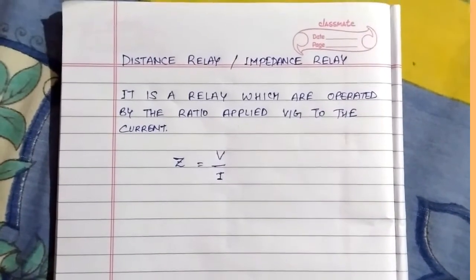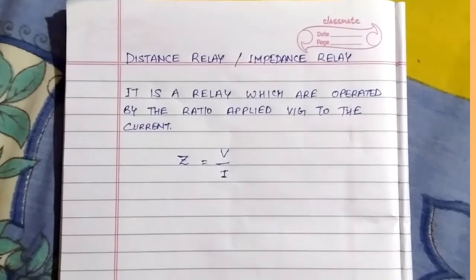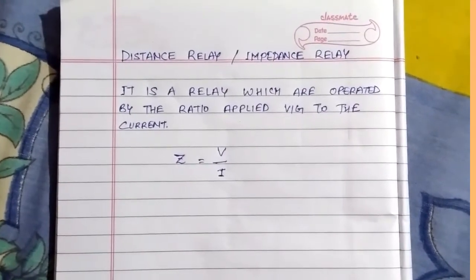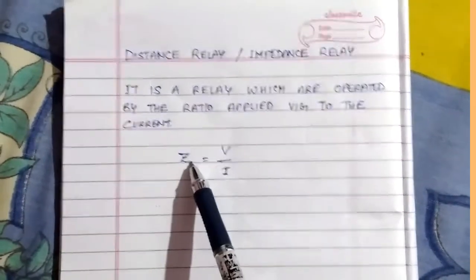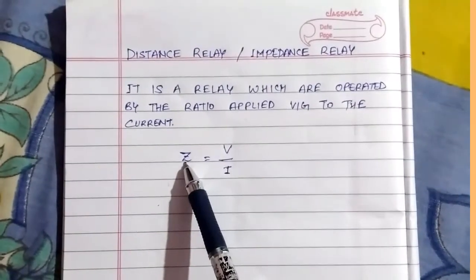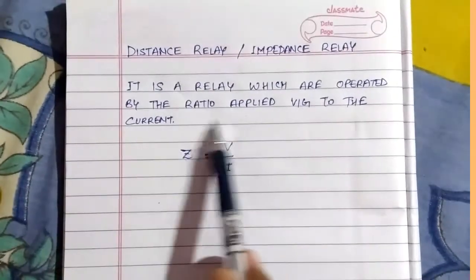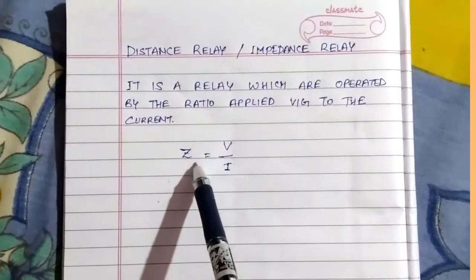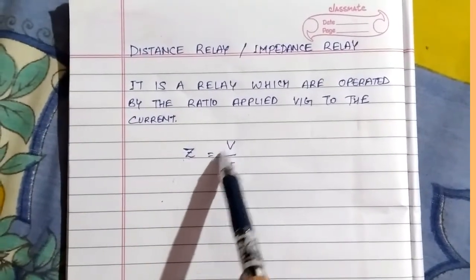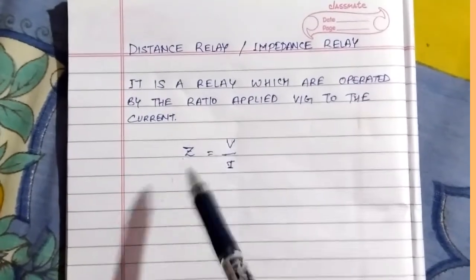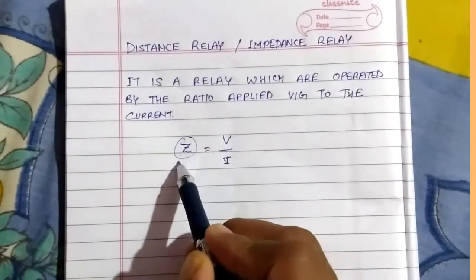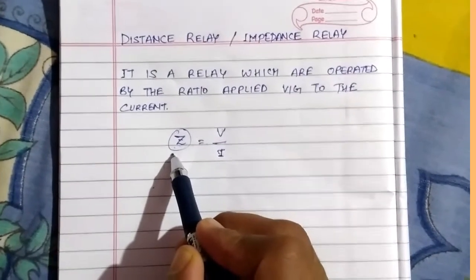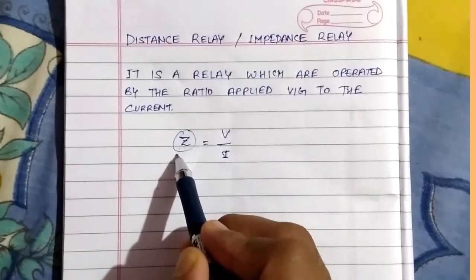Today we will discuss the distance relay, which is also known as the impedance relay. It basically works on the principle of change in the impedance of the line — it is a relay which operates on the ratio of applied voltage to current, that is impedance V by I. If this impedance changes, the relay will activate the tripping mechanism of the circuit breaker.